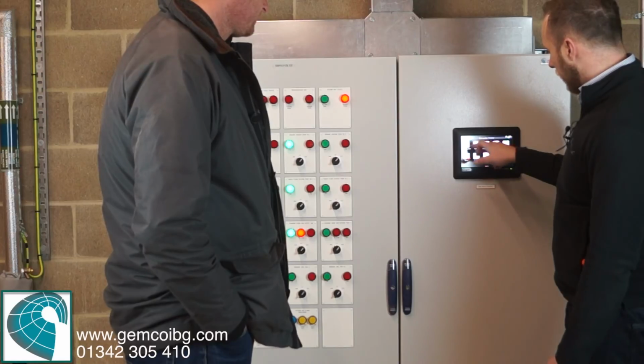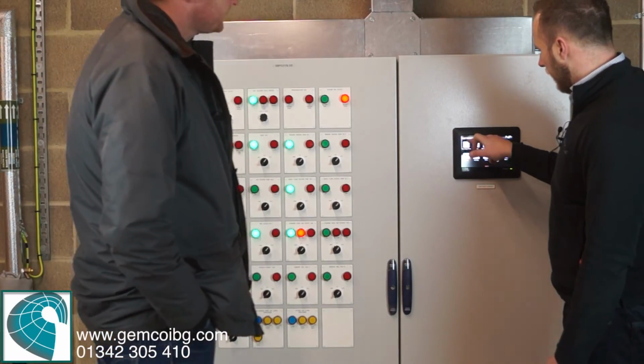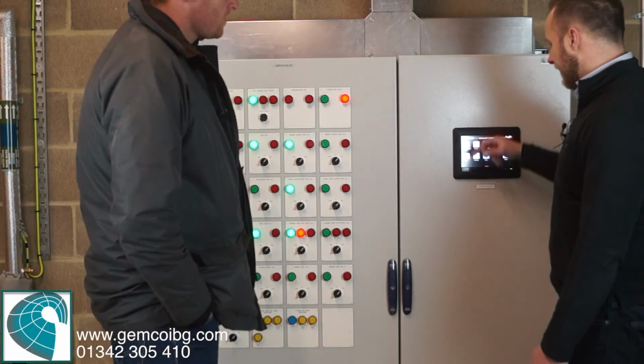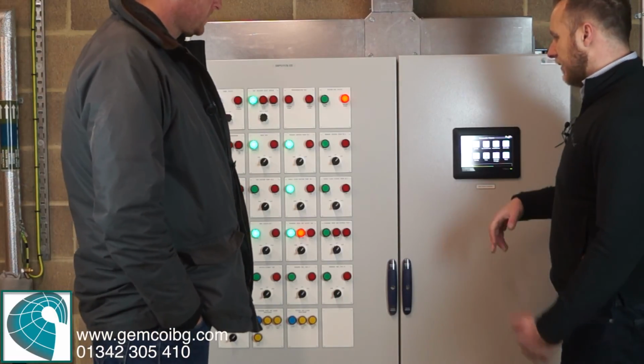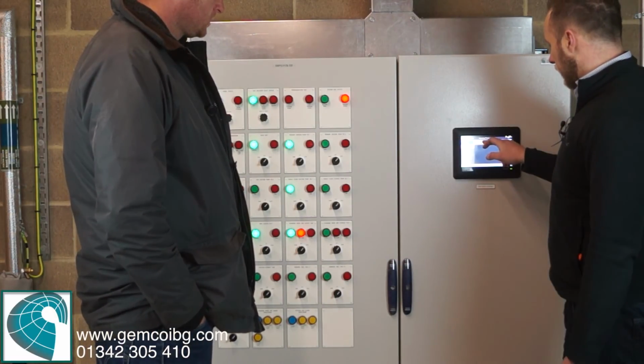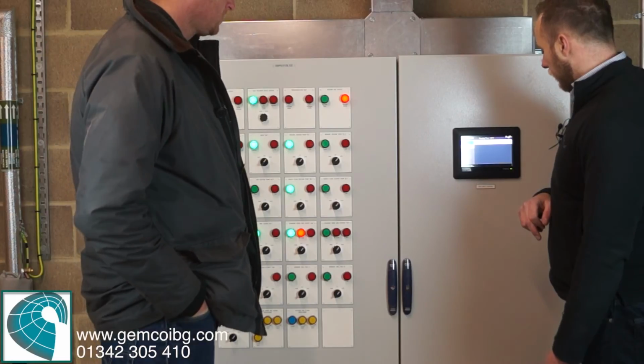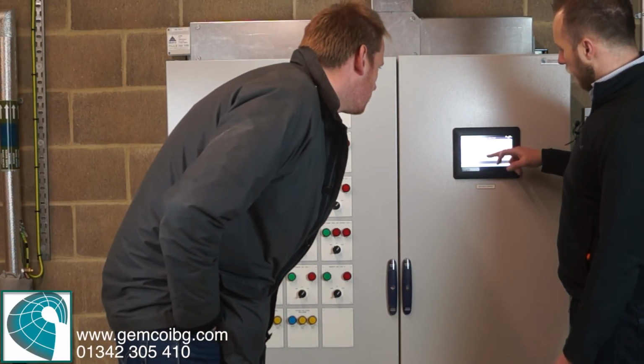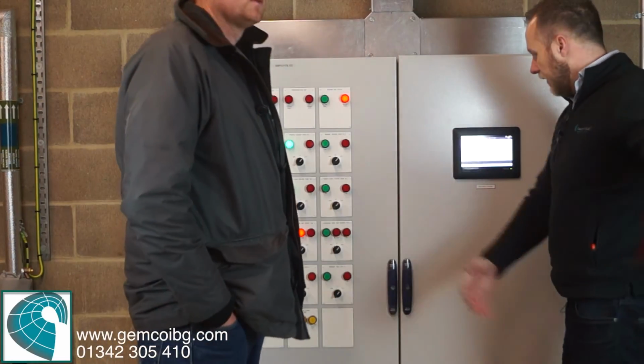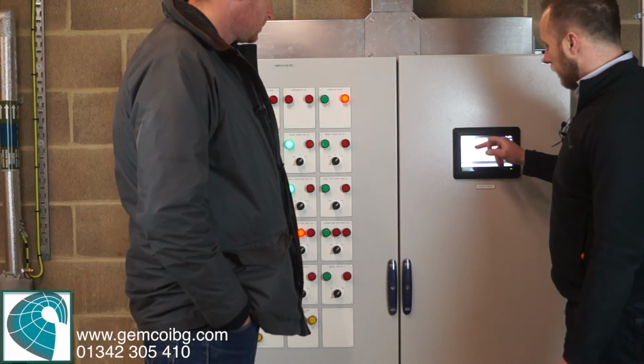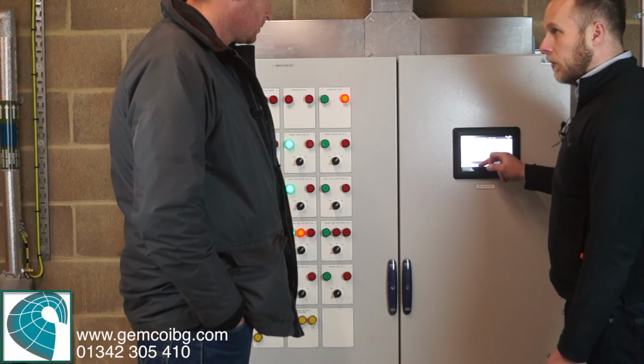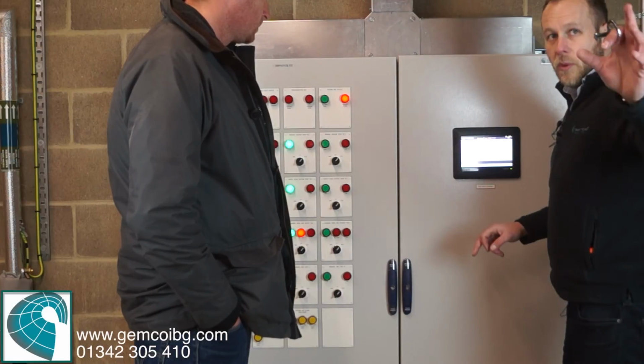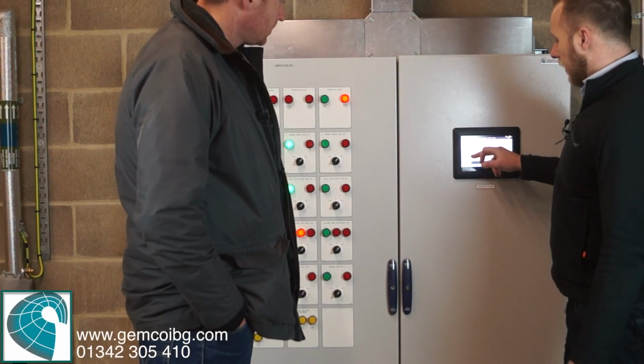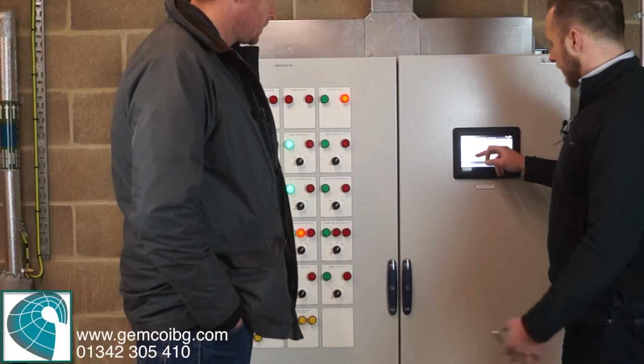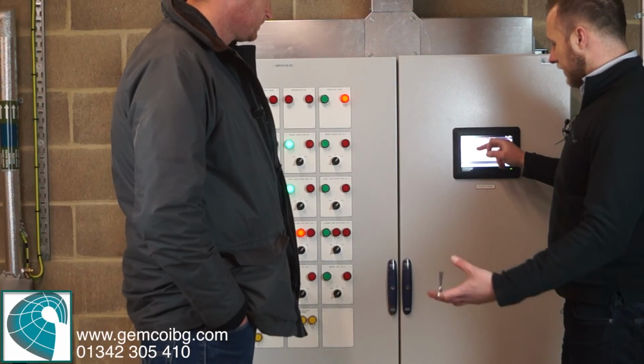So operating times, controls browser, those two there. Controls browser, you're going to find the settings. Operating times, you're going to find the time zone settings, which again, you go into time zones, click on boiler room, and you're presented with main plant, which is all of this plant in here, and then we've got the changing room, kitchen, honours, drying room, hot water. So the hot water is when you want your hot water on. Drying room is when you want that ventilation on in there. Honours, same. Kitchen, same.